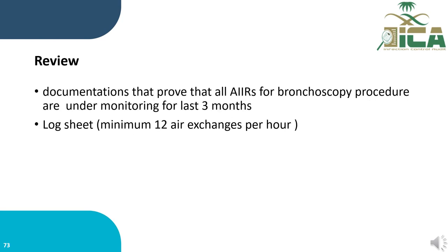You need to review the documentation that proves that all airborne infection isolation rooms for the bronchoscopy procedure have been under monitoring for the last 3 months, to ensure continuous monitoring of negative pressure and that all airborne infection isolation rooms are under negative pressure at all times.